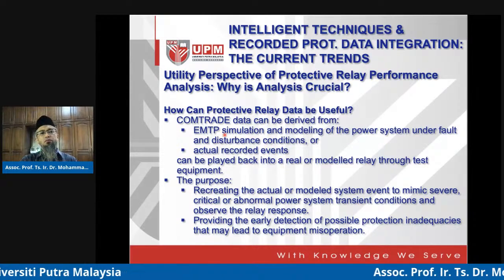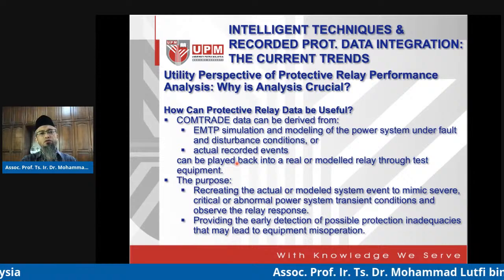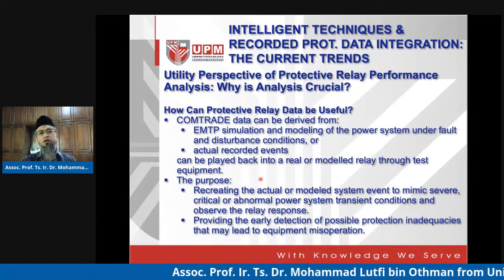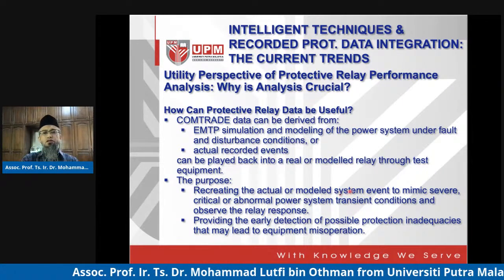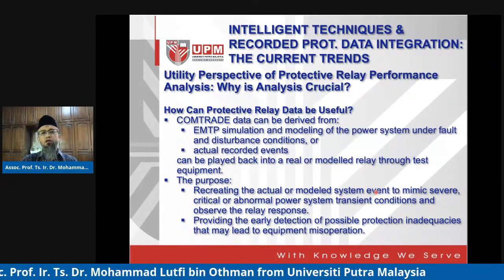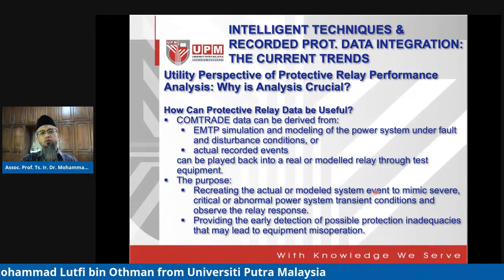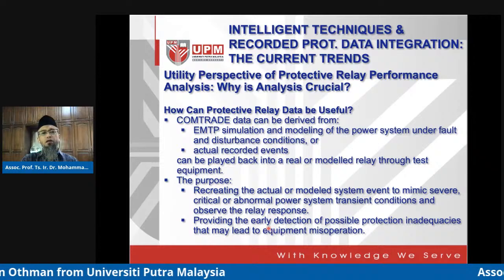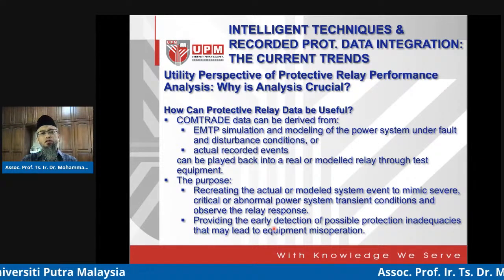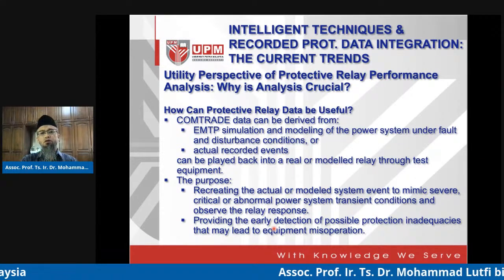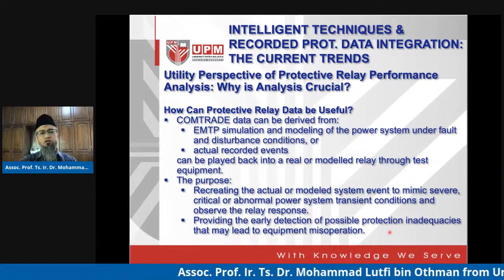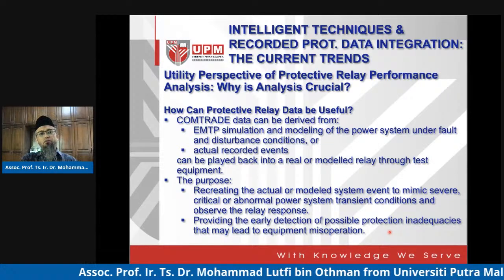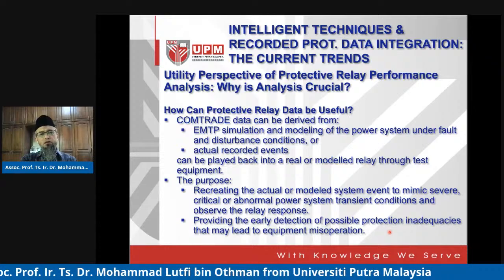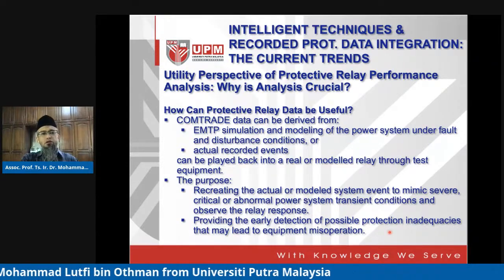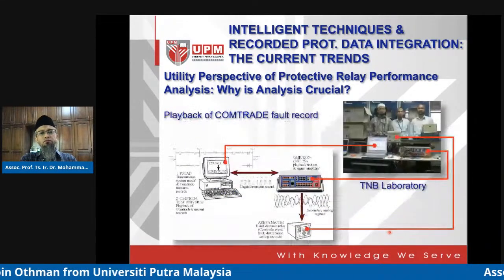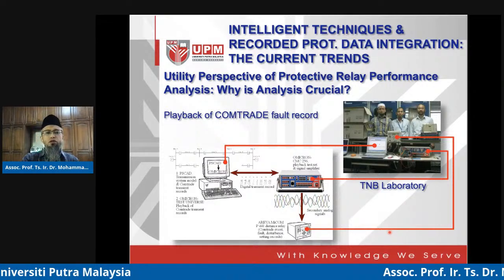Playing back the Comtrade data is very useful. The purpose is to recreate the actual model system event, to mimic the severe, critical, or abnormal power system transient conditions. By doing so, we can also understand the possible inadequacies in the protection system. So we can play back the Comtrade data in a real relay or in a model relay, depending on our research purpose.